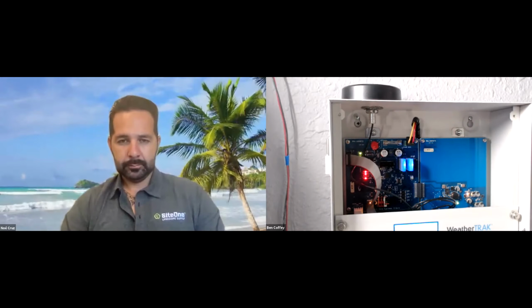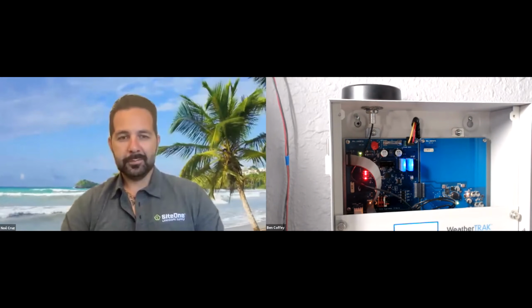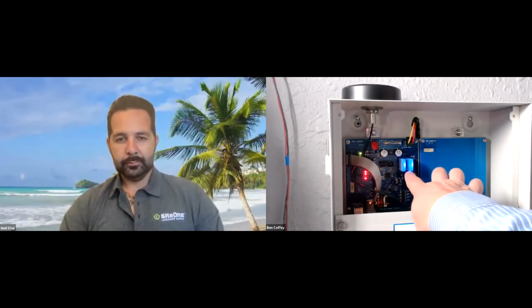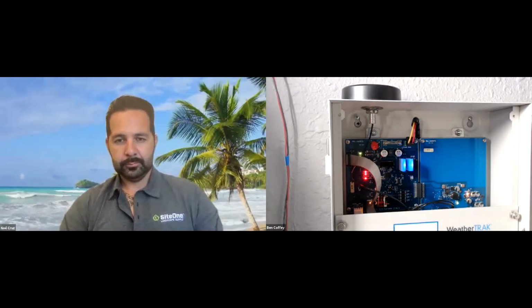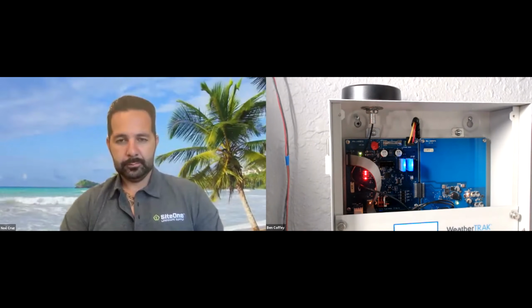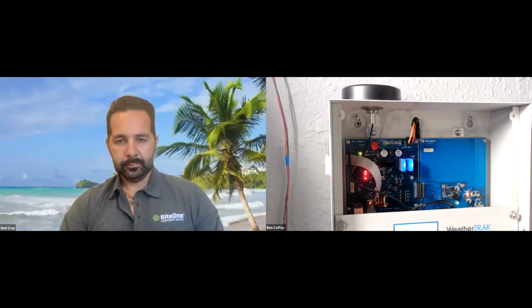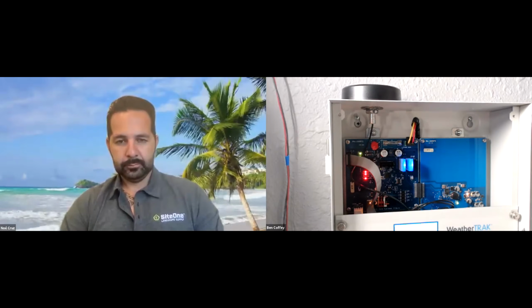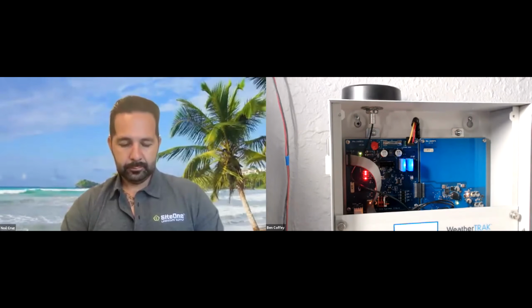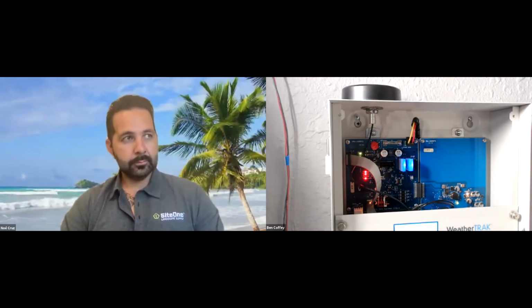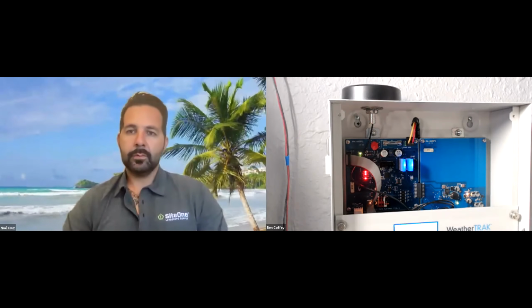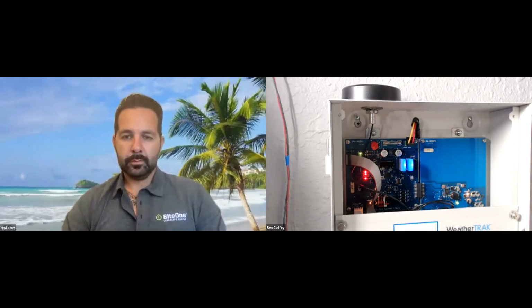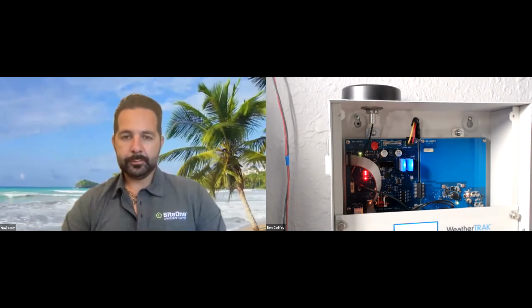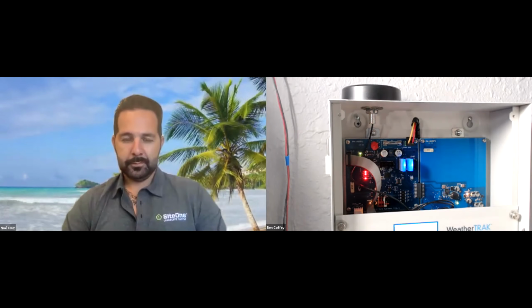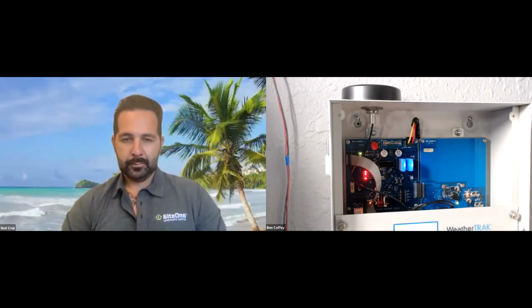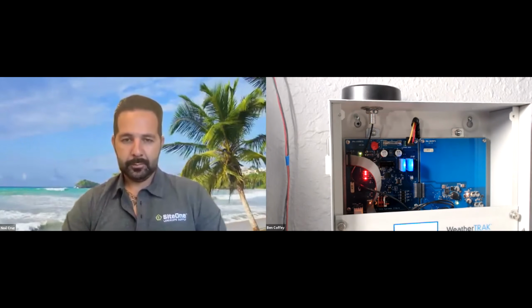When we came out with the 200 station, all I had to do from a hardware perspective is these little keys right here. When you get an H2O 2-wire, it comes default to 48 stations. If we add one of those keys, that bumps the configuration up to 96 stations. So that expansion was easy, from 48 to 96. The only hardware difference, other than the extra field components needed to run more stations in the field, is adding that second key and then doing a firmware upgrade. The only hardware part is plugging in that little glowing blue key, and the rest is firmware.